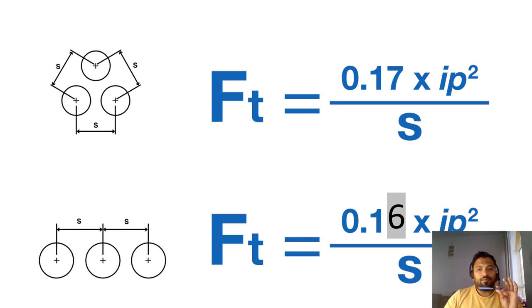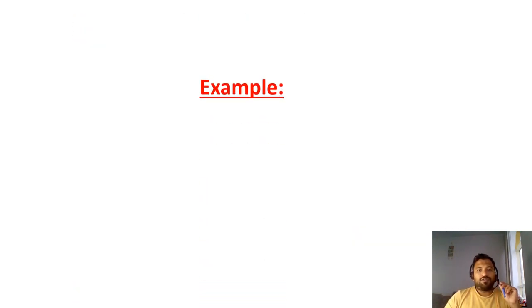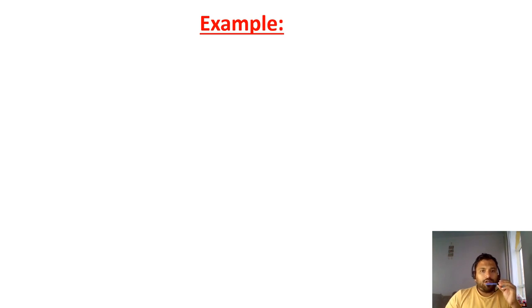So we have two different formations. One is the trefoil format and another one is the flat format. In the trefoil format, the formula is same, 0.17. While your cables are laying a flat format, then you should be calculating this one, 0.16 into Ip square by S. Only difference, very little bit difference between both.